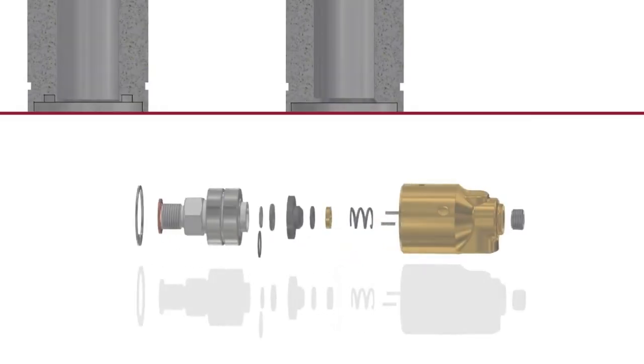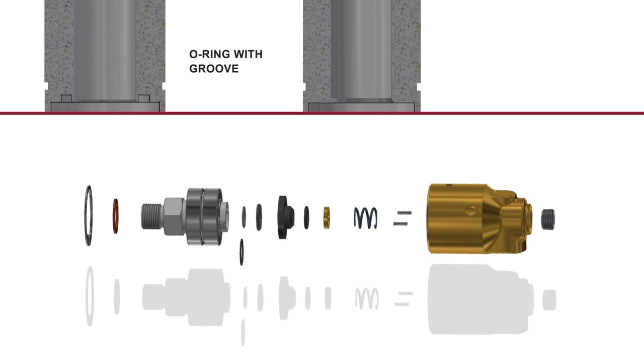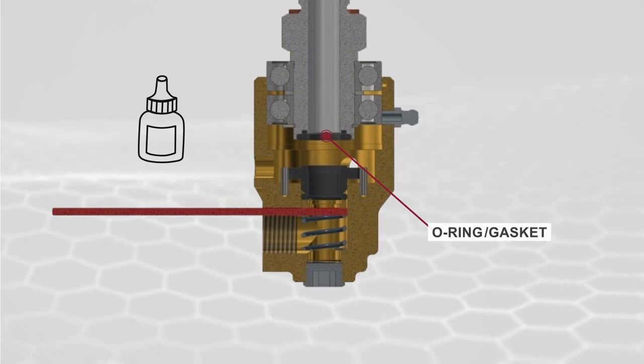If your rotor package has an o-ring with a groove, use the o-ring. If your rotor package has a flat surface with no groove, use the gasket. Grease either the o-ring or the gasket from the C kit depending on which type of rotor package you have to hold the rotor seal into place on the rotor package.